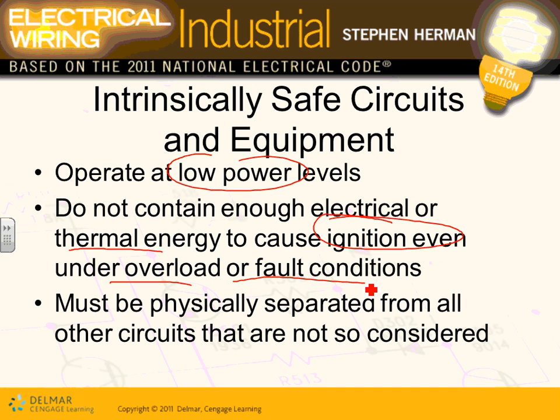And because of that, they must be physically separated from all other electrical circuits. You have to separate them from other circuits. You put them in a conduit, you mark them intrinsically safe system every 25 feet with a blue conduit, and you don't put anything else in them. They're typically used for instrumentation.